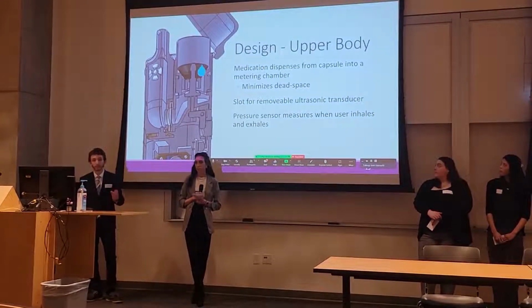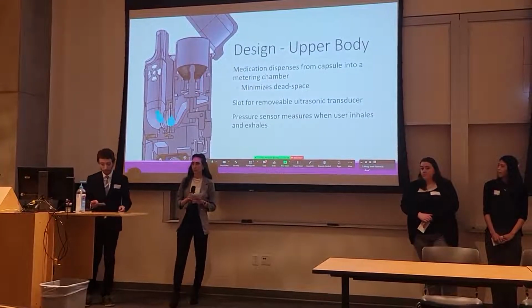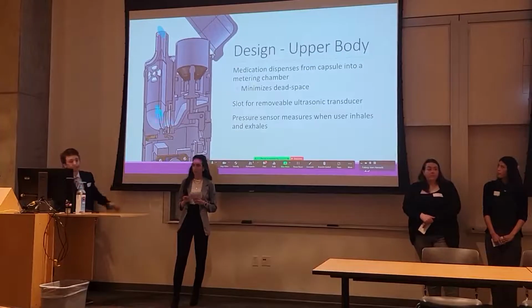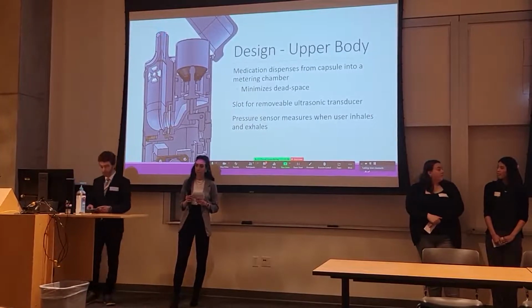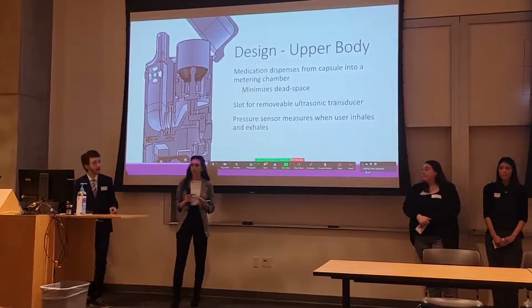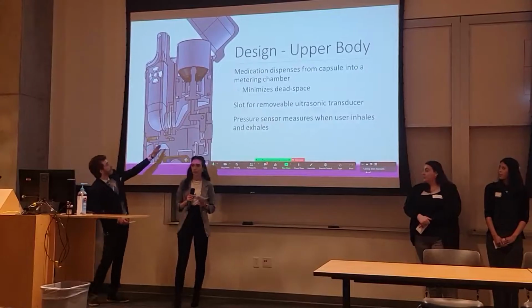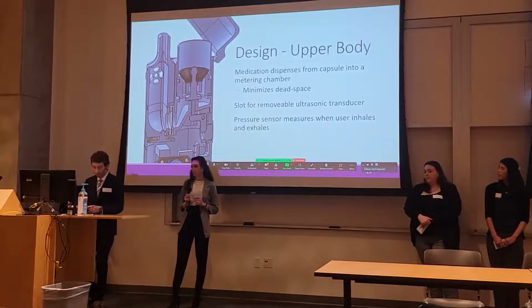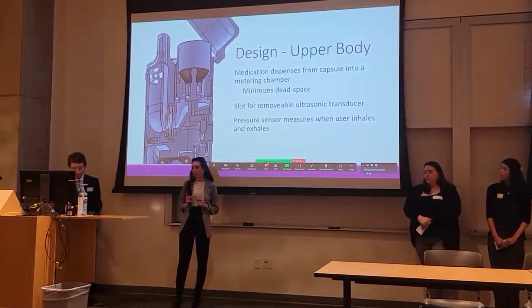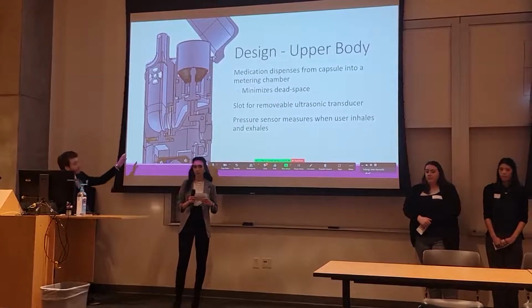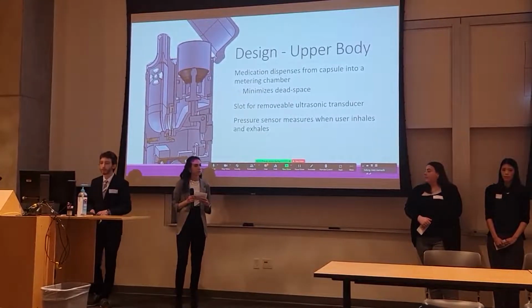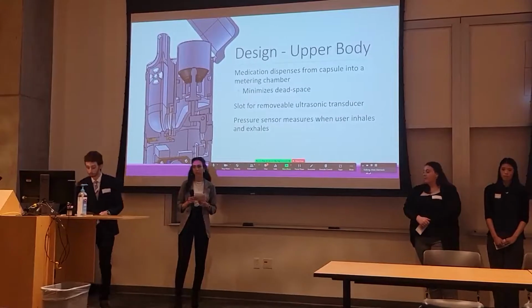When the medication is released from the capsule, it enters a metering chamber that is sloped to minimize medication waste due to dead space, before finally getting atomized in the ultrasonic transducer here and entering the mouthpiece. There, a pressure sensor helps to nebulize medication only when the user inhales, to precisely meter the dose that's delivered to the patient.